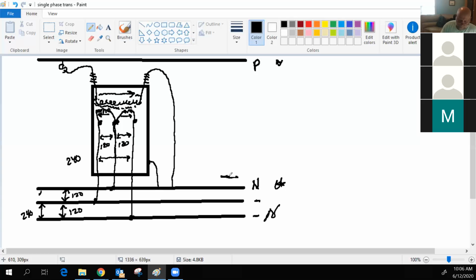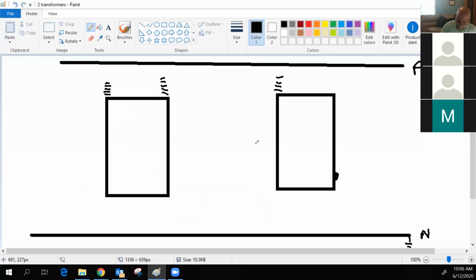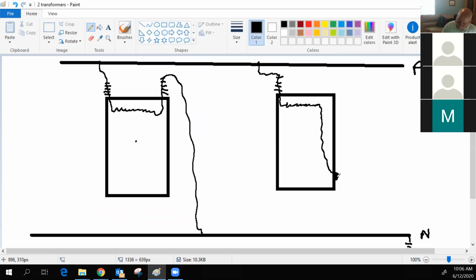All right, I'm going to go into another one here. Just like we talked about on the video we watched with transformers, this transformer, the primary comes in, goes through the bushings, goes out, grounds to neutral. Comes into primary on this side, goes through windings, instead of going out of a bushing on the top, it actually goes out through the bottom. It's connected to the tank, and the tank is grounded. We all got that correct?